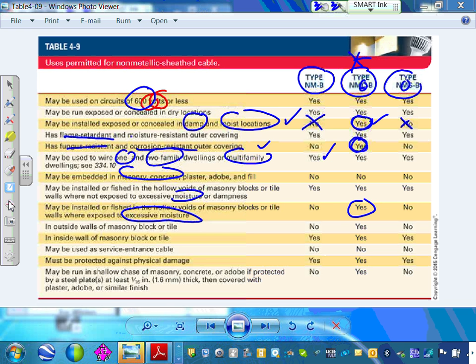I can think of barns as a good example where excessive moisture, you can use. Basements, no, basement you can use that one. Barns, what about the underground? No, that can be used underground. That's wet. Anything underground, remember, wet. A parking ramp, but this would be depending on the parking ramp. This would not be an approved wiring method though.